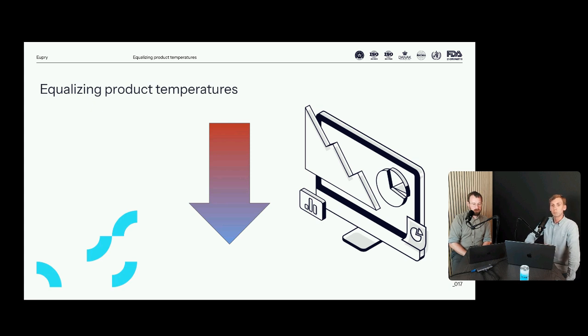People also ask, is it compulsory to perform power failure and open door tests when products are in place? Another good question. It's compulsory, or at least mandated by the standards and guidelines, to perform these tests, but it doesn't necessarily have to be with real products, because that could ruin quite a lot of product. What we often see in temperature mappings is the use of dummy products of roughly the same size and thermal mass placed on the shelves, and the studies are performed on those, since using real product would be a high risk and could make for a very expensive mapping. Great question.